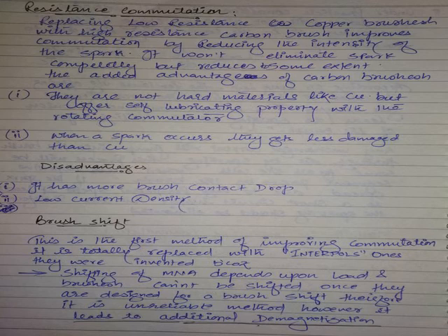Now, one more thing here is, the increased resistance in the brush will not affect the current which is connected in this part. I'm repeating, the increased resistance in the brush will not affect the current flowing in this part. You are not replacing the copper brush with wood or plastic. You are just replacing it with a slightly higher resistance brush which can collect current. Don't think that the current is also opposed by this brush. If you observe the trailing pole tip and the leading pole tip region, under the trailing pole tip region, the brush contact area is diminishing in nature, is decreasing in nature.